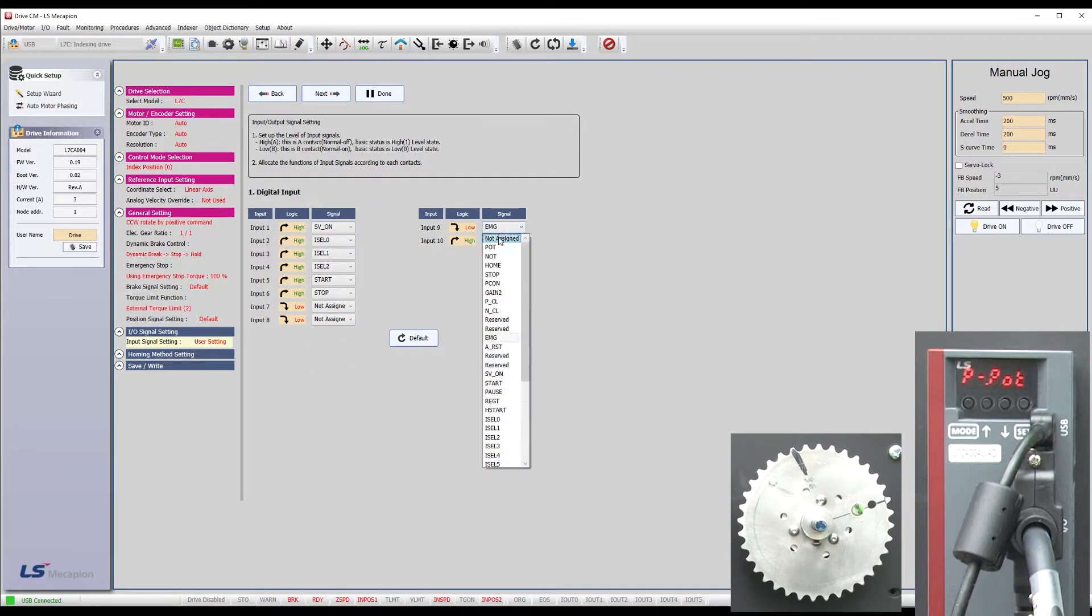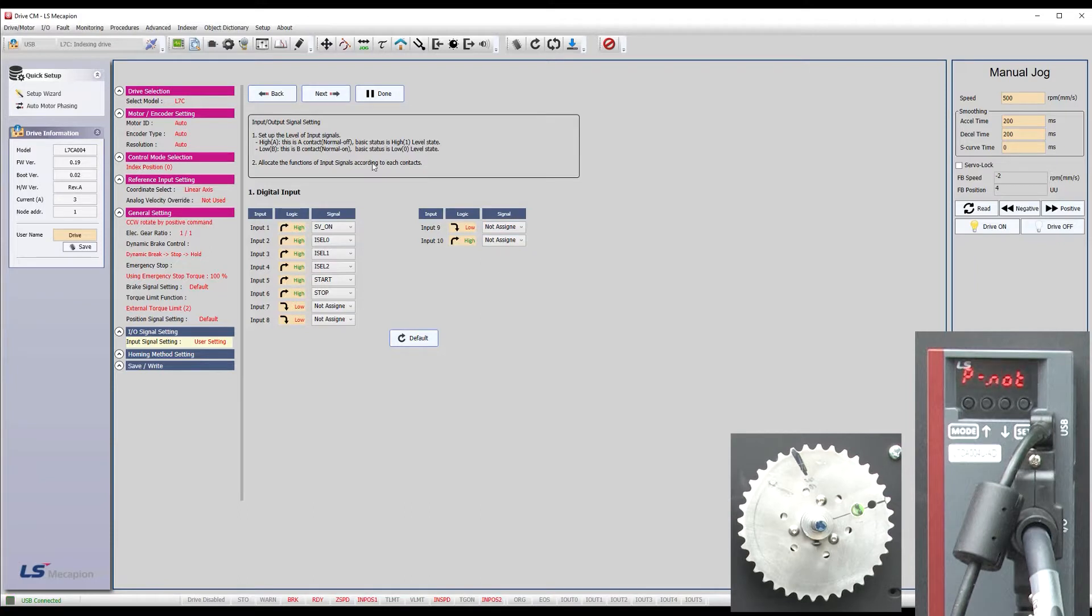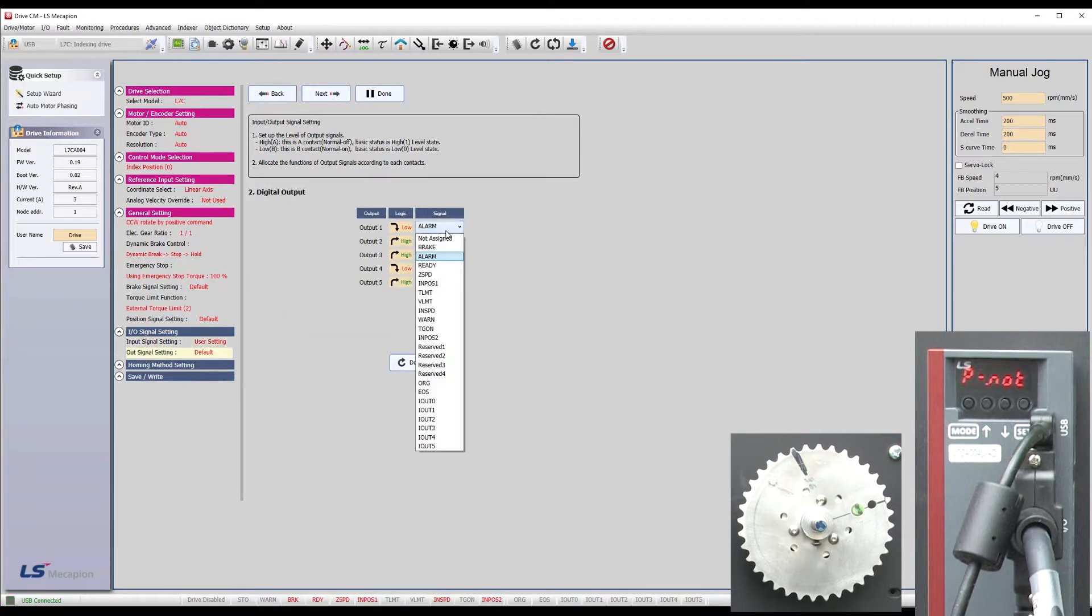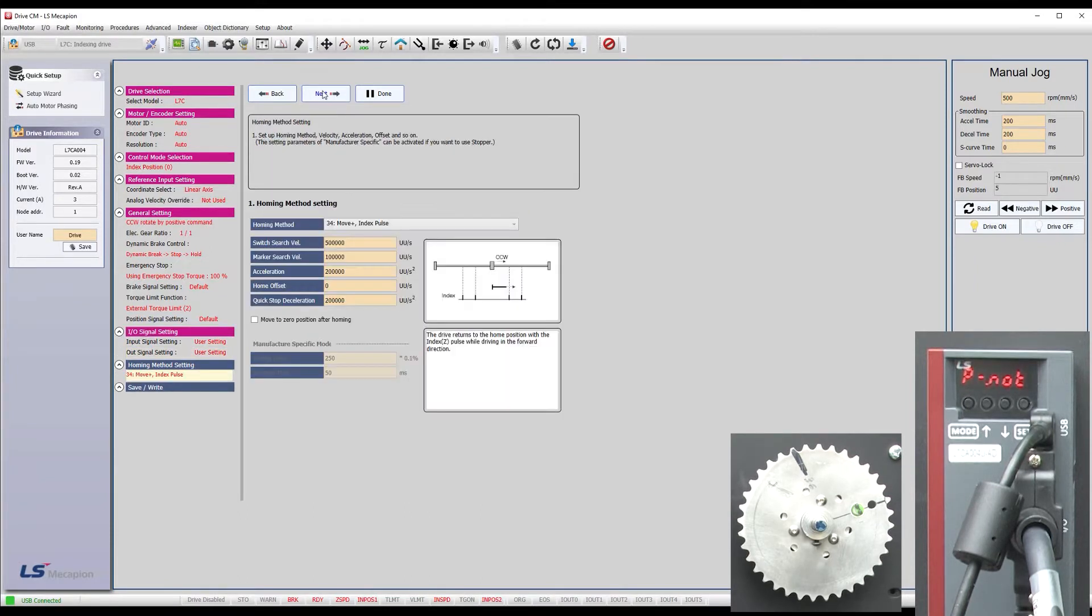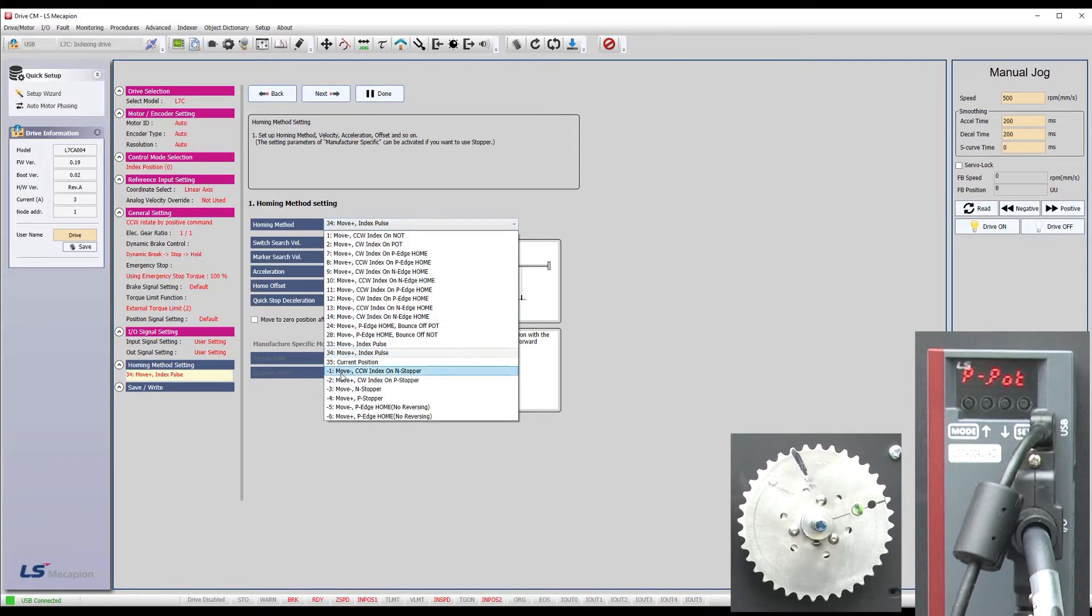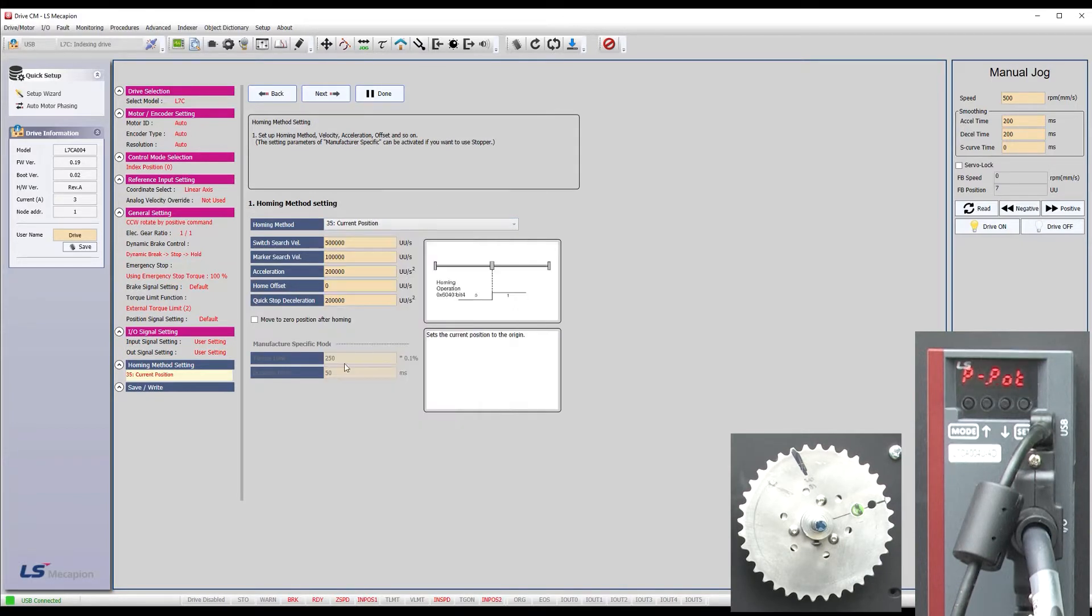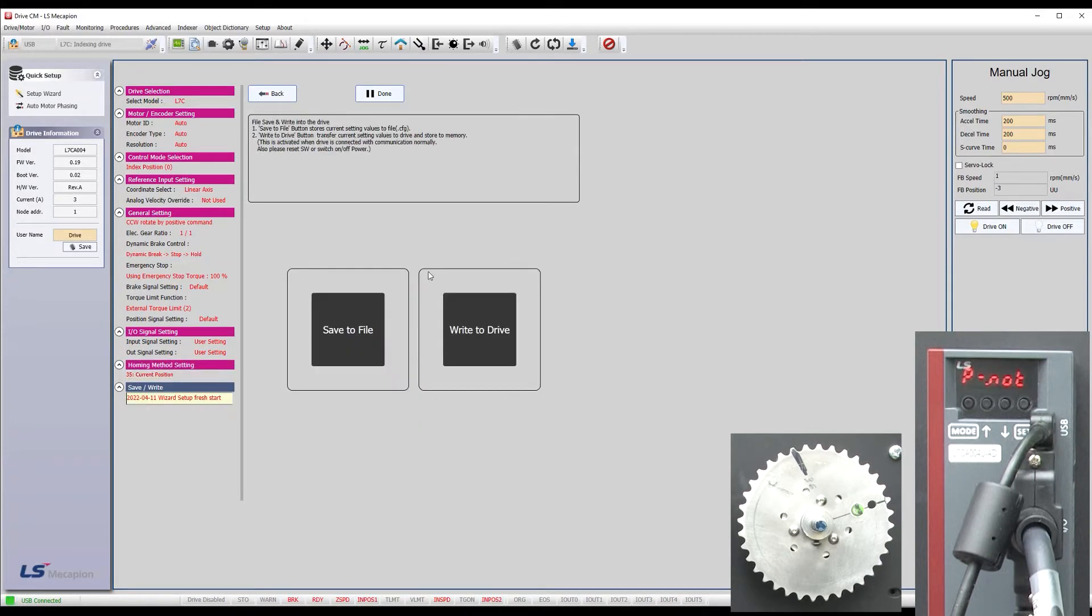The rest of these aren't needed. Now I like to see the index outputs. They are handy for debugging things. And I like to keep homing mode 35 handy so I can quickly reset the position register. Write that to the drive.